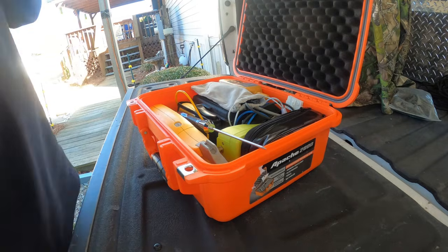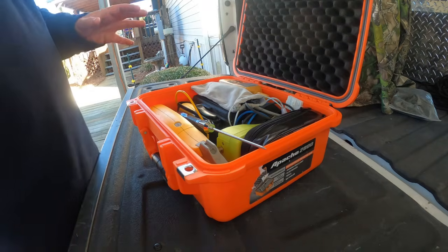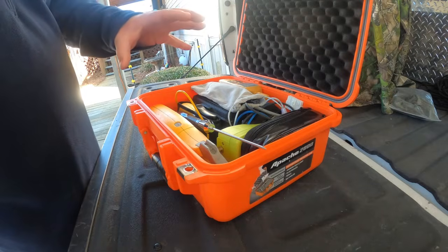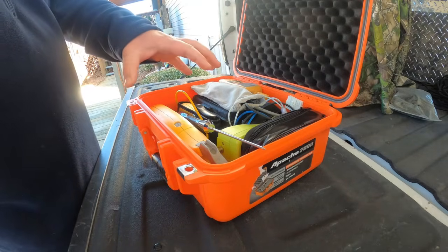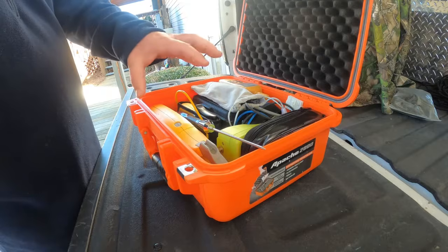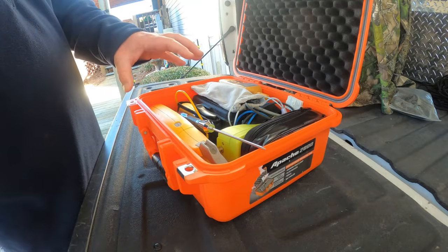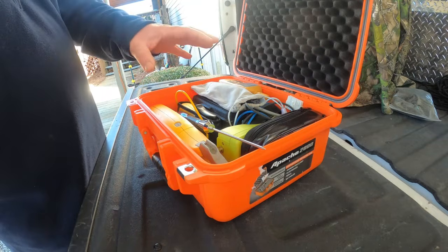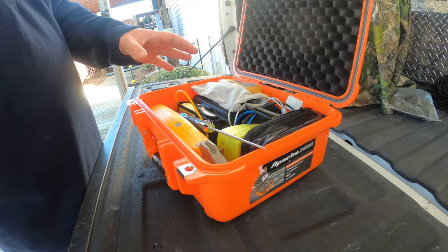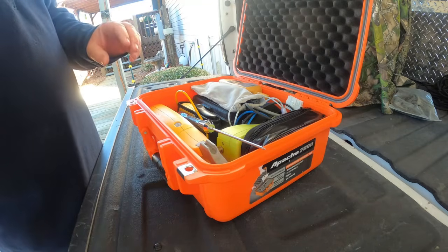So you want to keep that in mind. Typically you want to check one. If you go to it and it's rocking and shaking in there, then typically you've got high voltage, you've got low voltage going to that motor. It's going to be the motor or the module. Sometimes you can replace the module, sometimes you need the whole motor.